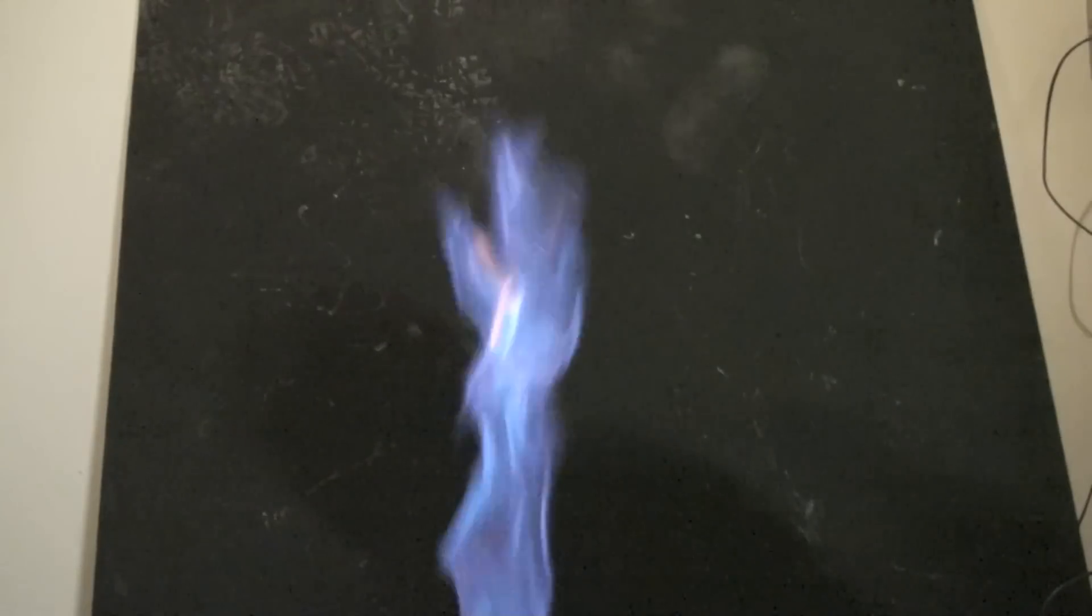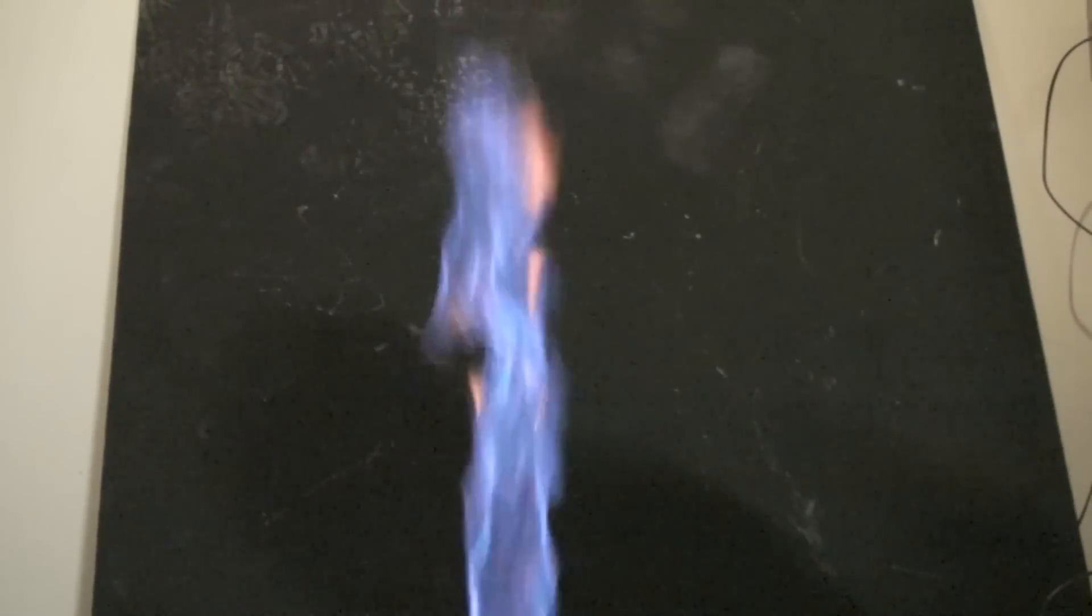If I put too much air in it, now if you listen close, you can hear it's kind of ruffling. It's got really yellow tips, but the flame is being cooled down because there's too much primary air coming in.